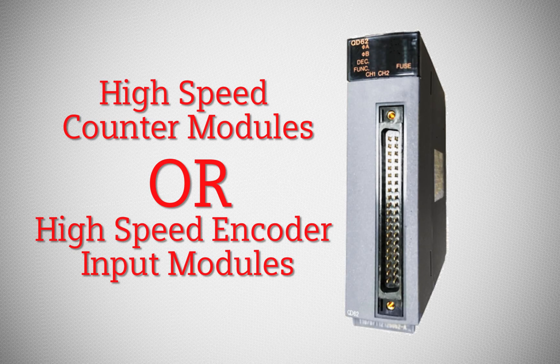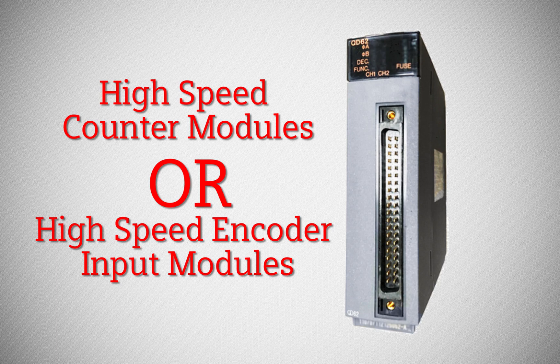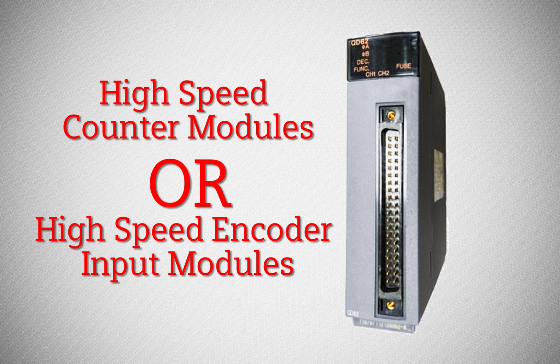In these situations, specially designed modules like high-speed counters can be used to ensure no pulses are missed. These counters are designed to work independently from the CPU scan, meaning they have their own processor dedicated to tracking the number of pulses coming in. These high-speed cards then feed the count over to the CPU when it is required.